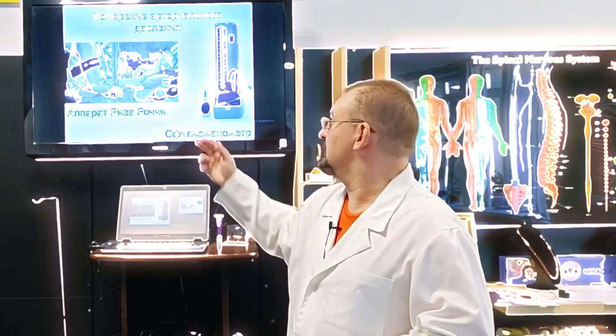What was the essence of this device? So, a flexible cuff with a soft rubber balloon was carefully put on the upper arm, specifically on the shoulder area, and you could then easily pump air into it, and the precise manometer clearly showed to what exact pressure the mercury column had been pumped up. That is to say, precisely how much air was contained within the cuff at that moment. And the mandatory condition was that the cuff had to be inflated so much that it completely blocked the artery, the brachial artery that carries blood to the arm.